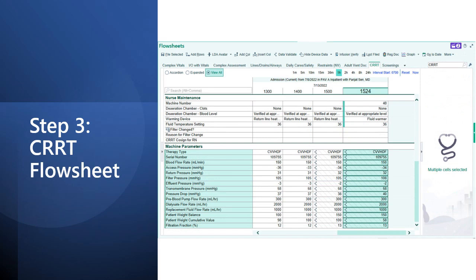In continuing to chart on the CRRT flow sheet, the nurse maintenance is going to consist of the machine number, and that's the big black number that we have taped on the front of every machine, as well as on the left-hand side with the label maker. It is not simply the 20 that is right below the heparin syringe. That is reflecting the fact that it's a 20 milliliter heparin syringe. We're also going to attest that the nurse has looked at the deaeration chamber, seen no clots, and moved it to an appropriate level, and then what warming device we're using. So the Thermax is a fluid warmer, and it's typically set to 36 degrees.